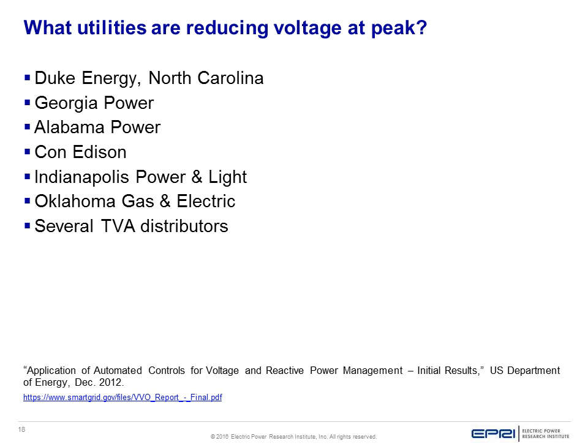So the top two utilities on the list were both pioneers in pretty aggressive programs as far as squeezing the most out of the benefits you can get at peak by flattening voltage profiles and targeting and using capacitors and voltage regulators. But it's tricky to reduce voltage at peak because that's when the load's the highest and that's when you get the most voltage drop.